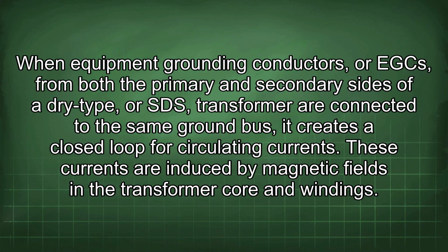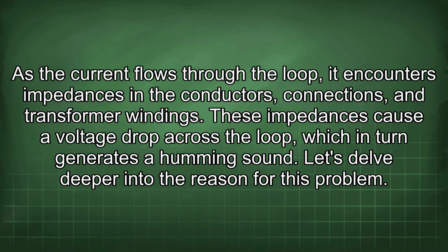When equipment grounding conductors, or EGCs, from both the primary and secondary sides of a dry-type, or SDS, transformer are connected to the same ground bus, it creates a closed loop for circulating currents. These currents are induced by magnetic fields in the transformer core and windings. As the current flows through the loop, it encounters impedances in the conductors, connections, and transformer windings. These impedances cause a voltage drop across the loop, which in turn generates a humming sound.